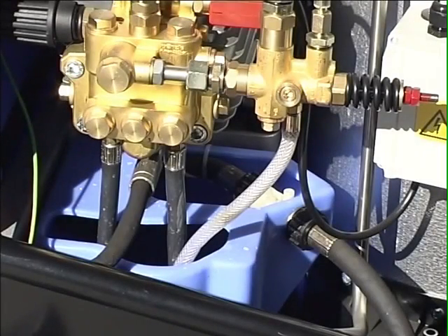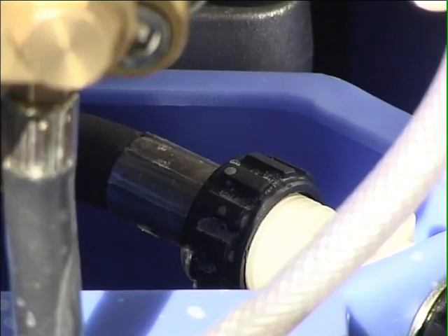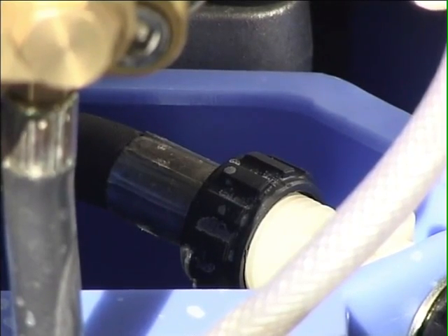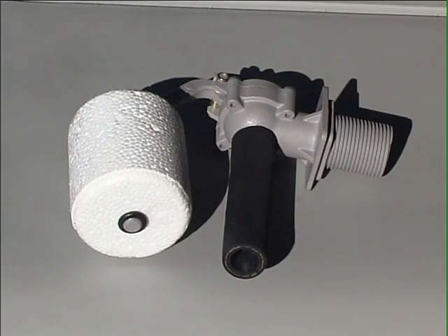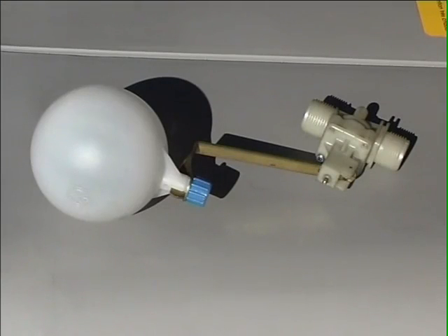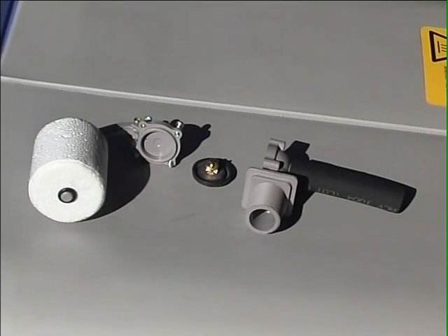Floater may be dirty or defective. It is in the water box. There are 2 floater versions. This is the new version. Basically, both versions are interchangeable with some minor adaptations. You can take the floater apart for cleaning. Check for permeability of holes in the membrane.